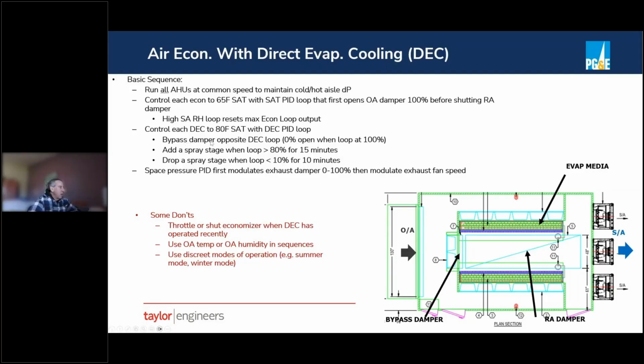It's going to modulate the bypass damper opposite the DEC loop. The damper will start at 0% open when the loop is at 100, actually sort of the other way around. When the loop is at 0, the bypass will be fully open, so we'll be mostly bypassing and only using a little bit of air through the media. And then as that isn't cool enough, we'll slowly shut the bypass and force more air through the media.